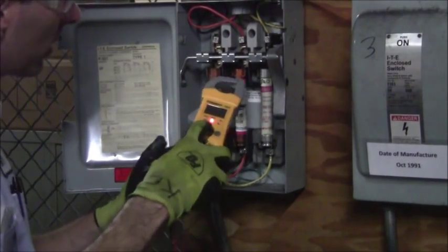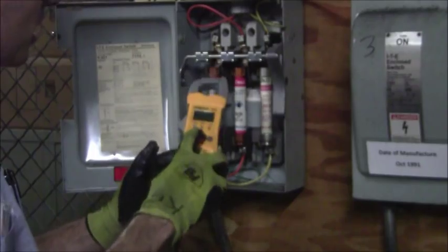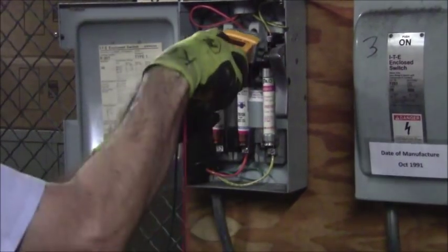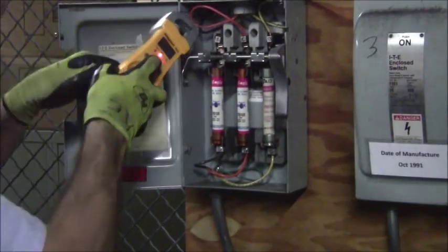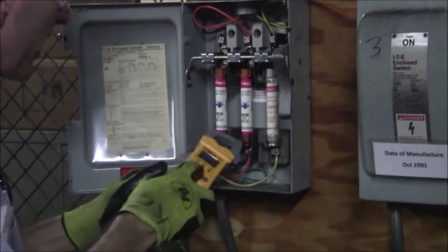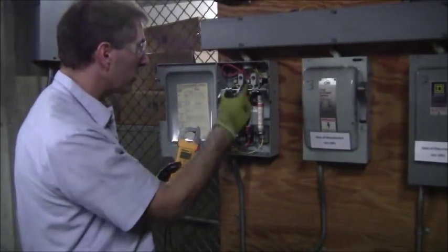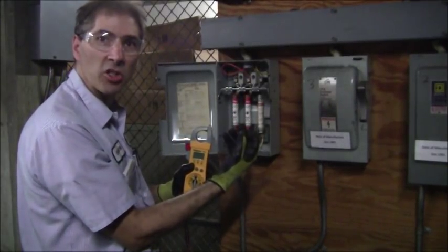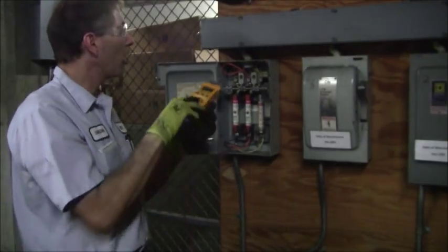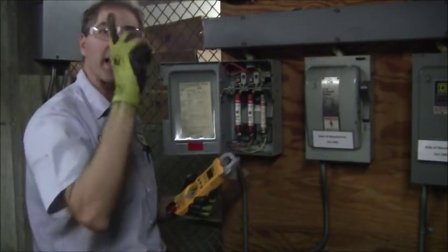Come up here. Okay, I'm starting to get some voltages, but that's just the induced voltage because I'm getting close to live electrical parts. See how the light came on? And you can actually hear that noise. But down here, you're getting nothing, which is telling me that the 3 phases or contact points have all opened properly. Also, I can physically see that they have pulled out, but I'm still going to take it one more step.